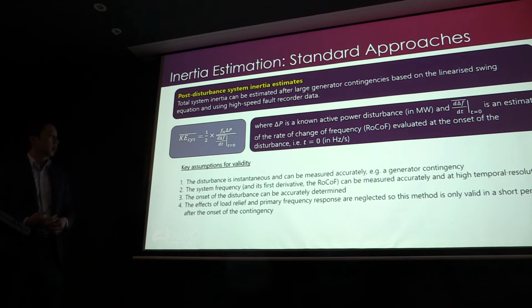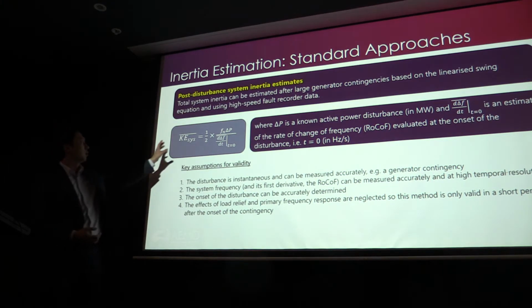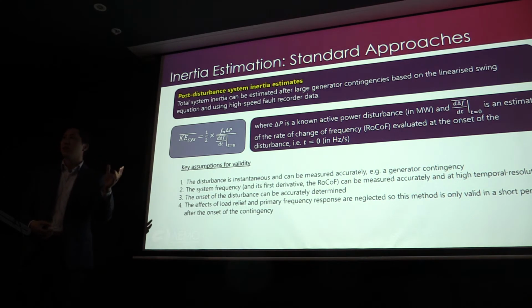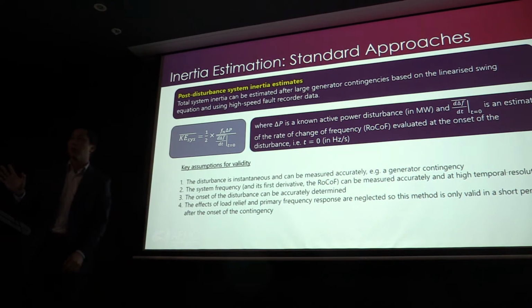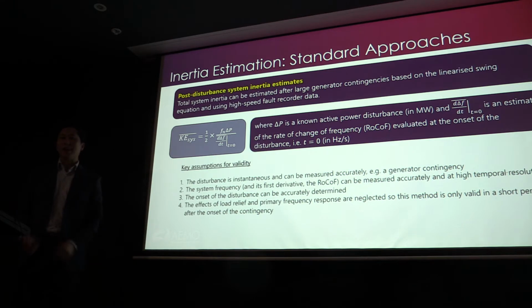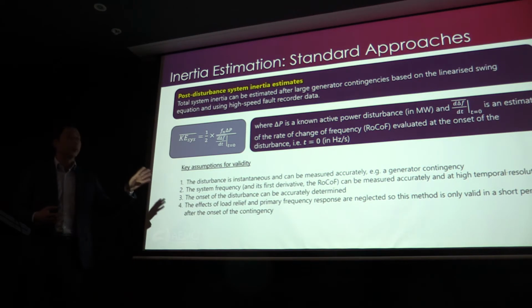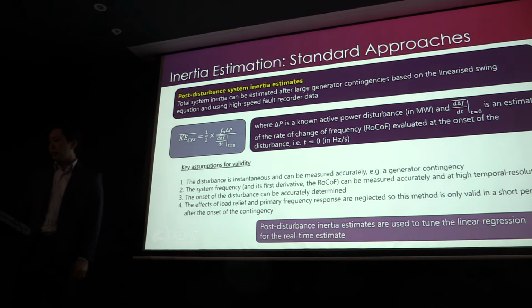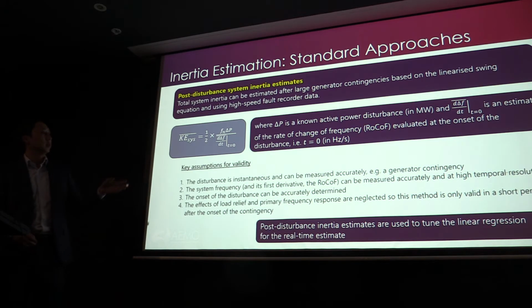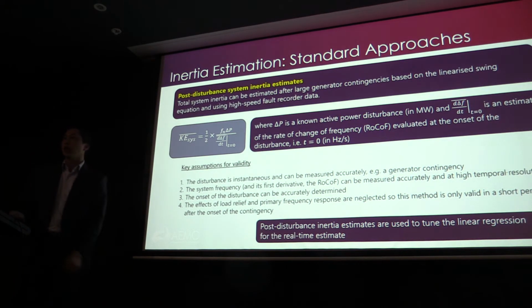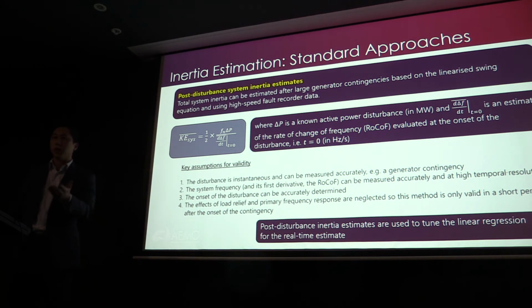And the effects of load relief and primary frequency response are neglected. So in the timescales that you're looking at, in that first half a second or so after a trip, you're assuming that there's no load relief and no primary frequency response. So no one's started acting yet. When you think about this, when you start having fast frequency response come through, this becomes a little bit more challenging. So we use the post-disturbance estimates to tune that linear regression, so we can create a real-time estimate of system inertia. That estimate will get used in the real-time frequency stability tool that Ali will talk about. And that's how it all fits together.